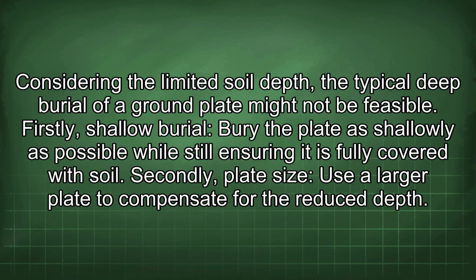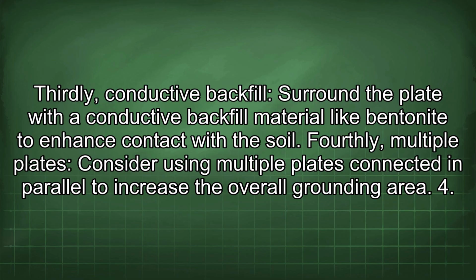3. Plate grounding system. A ground plate provides a large surface area for contact with the soil. Considering the limited soil depth, the typical deep burial of a ground plate might not be feasible. Firstly, shallow burial. Bury the plate as shallowly as possible while still ensuring it is fully covered with soil. Secondly, plate size. Use a larger plate to compensate for the reduced depth. Thirdly, conductive backfill. Surround the plate with a conductive backfill material like bentonite to enhance contact with the soil. Fourthly, multiple plates. Consider using multiple plates connected in parallel to increase the overall grounding area.